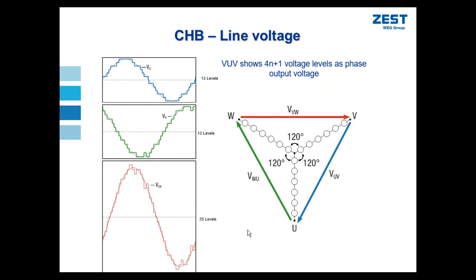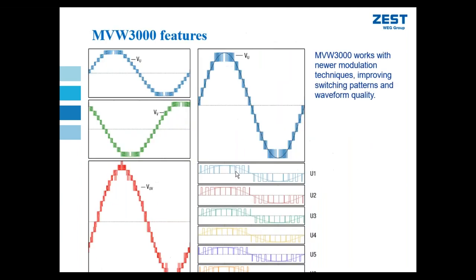Right. This just shows that waveform. This shows each phase to neutral waveform for U phase, for V phase, and then how they combine to increase the number of levels in my phase to phase output voltage. So the way that we investigated or showed how that switching works was a very simplified case, just to show how it works in principle.